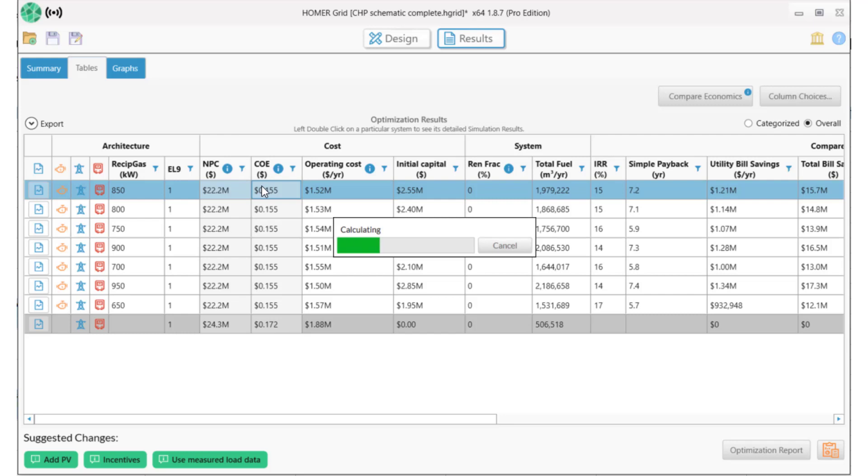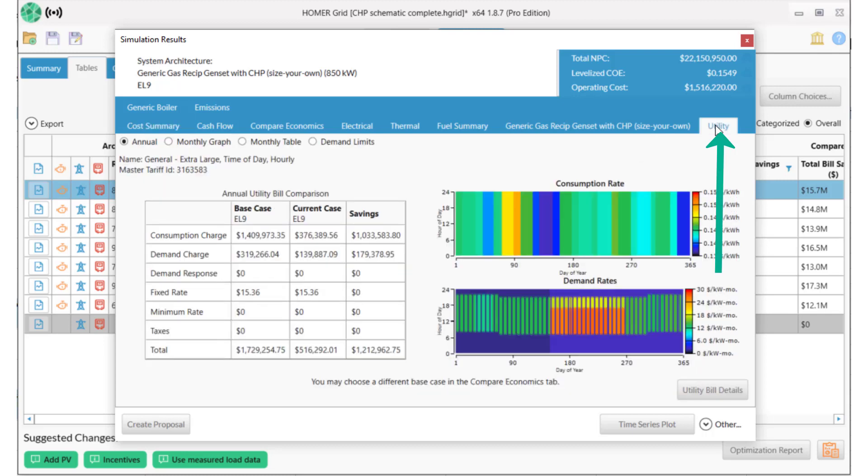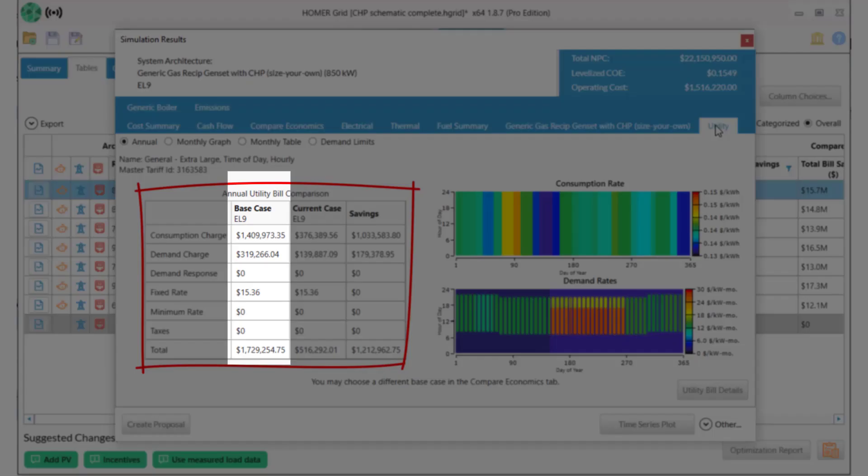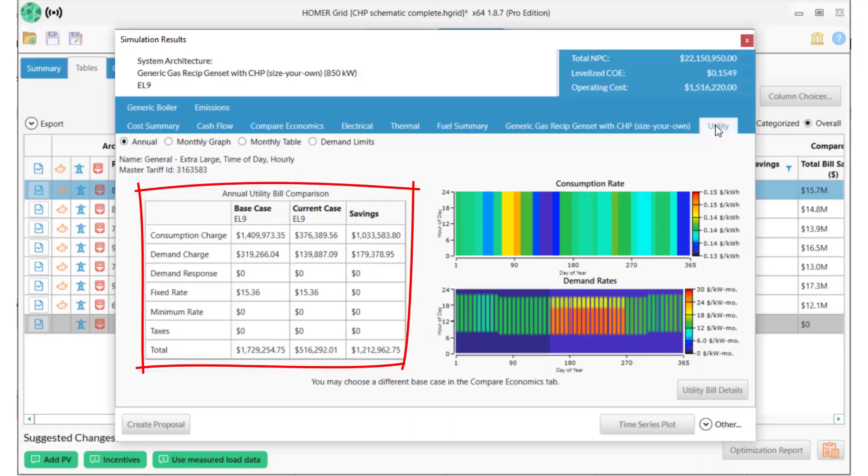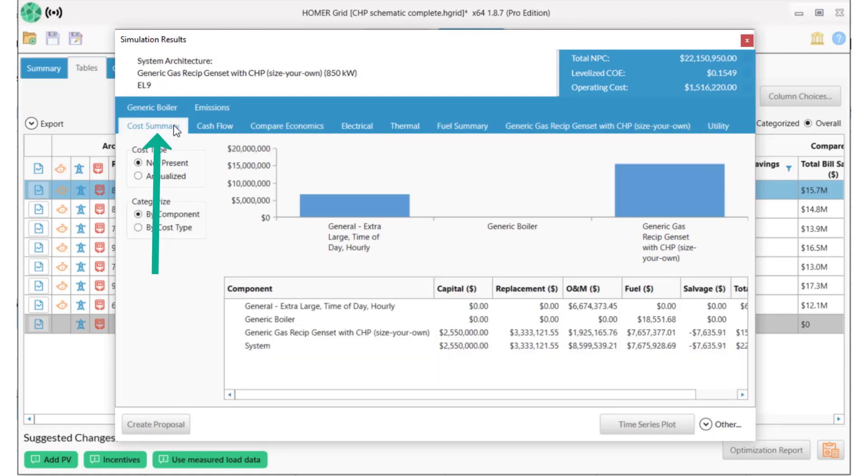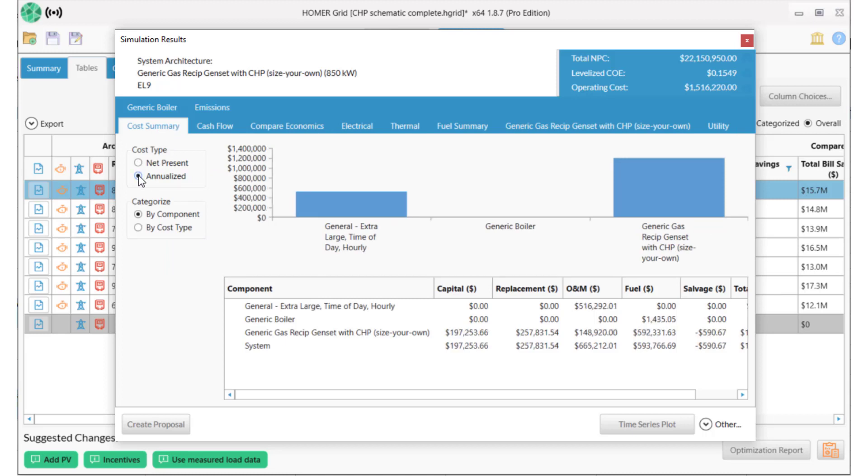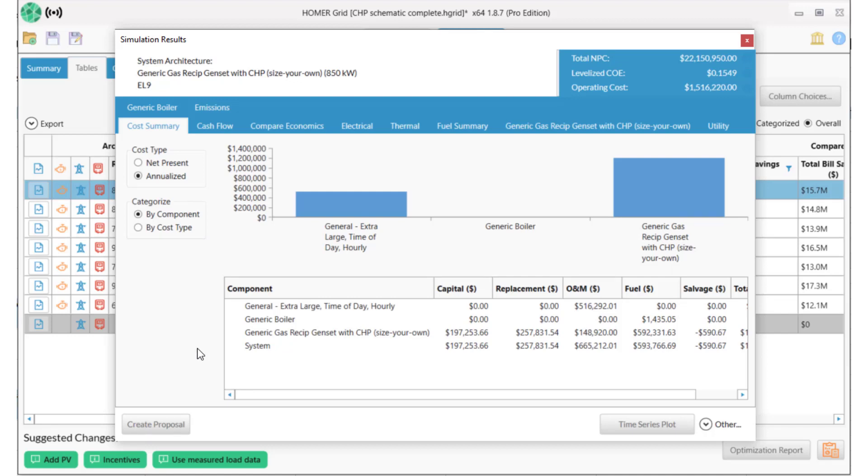If I look more deeply at the winning system and then go over to the utility tab, I can see the differences between the base case on the left and the system with CHP on the right. The total utility savings is over 1.2 million dollars per year. I'm spending money on fuel, which I can find here in the Cost Summary tab. If I change this to Annualized, I see that my fuel cost is about 600,000 dollars per year, but the overall system is saving about 1 million dollars per year in energy costs.